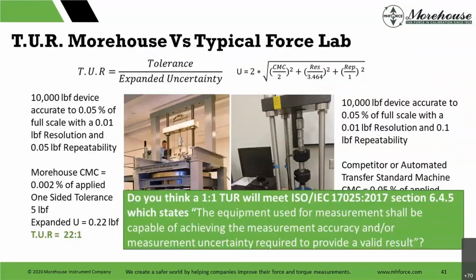When we look at this versus a typical force lab, I showed a picture earlier with 10 times the uncertainty. The TUR is really close to that, where this one is 22 to 1, and the one on the right, again we don't have animation, was 1 to 1. So it's the same formula, same lab, just a different type of standard, primary versus secondary. These are both found in our lab. The secondary machine is over in our torque lab. We use it for experiments and some other things, but we do not use it to calibrate customers' instrumentation. When we start looking at a one-to-one TUR, we look specifically at section 6.4.5: the equipment used for measurement shall be capable of achieving, right?